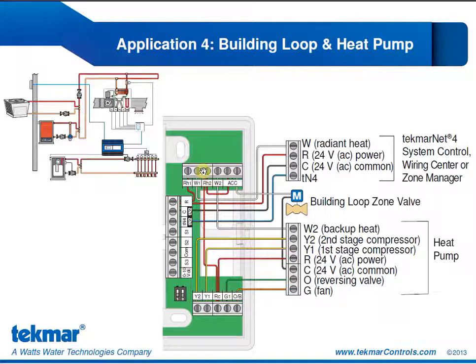Notice here as well that this time the accessory relay is controlling a building loop zone valve. So we have R from our heat pump coming in, coming up to RH2, and then jumped over to the accessory relay. Accessory relay brings that connection to the zone loop valve, and then the C comes back to the heat pump to complete the circuit.